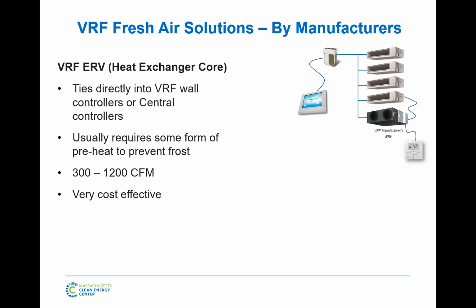The concept is energy recovery, right? You duct your exhaust air to one of these. It could be your kitchen, it could be your bathroom. Out of this, you then preheat your outside air that way. So you take that fresh air and bring it to the back of a ducted unit or to a ductless unit. Greg was explaining how there are some ductless units that have connections. That's the concept here. It's got to be engineered. It's got to be thought of.